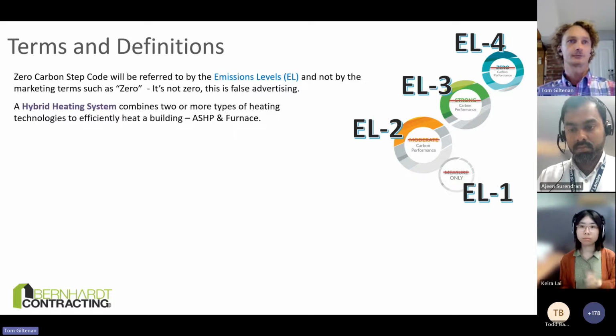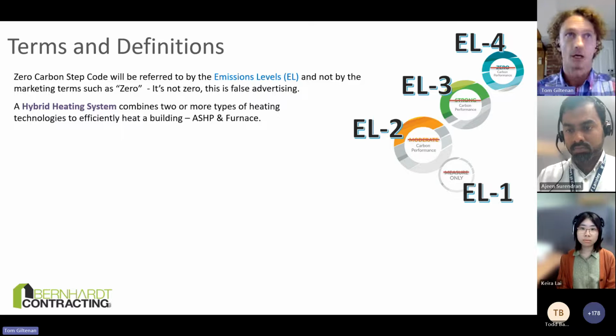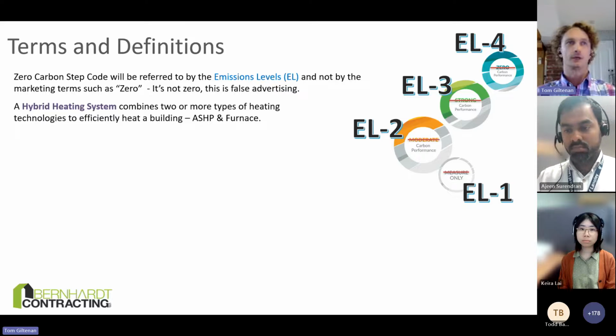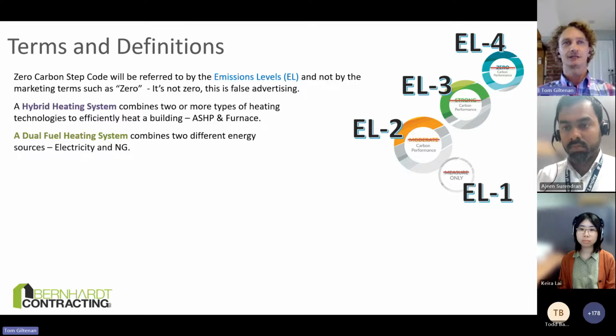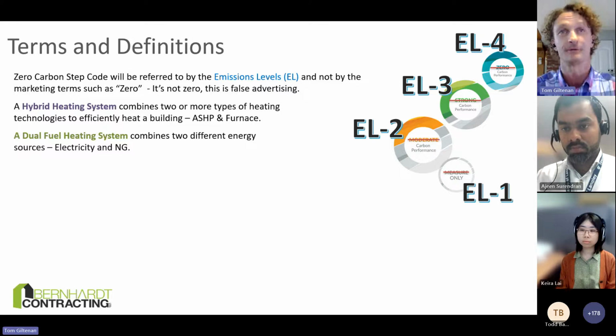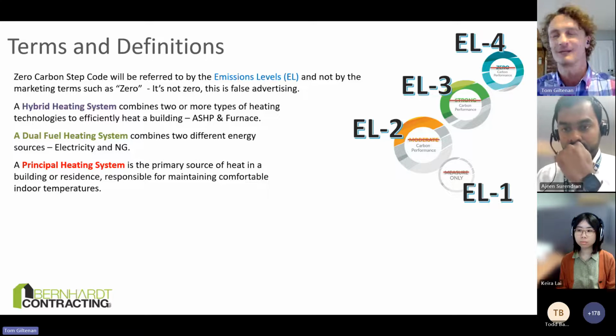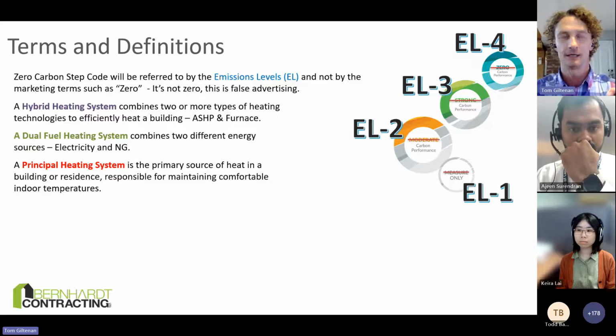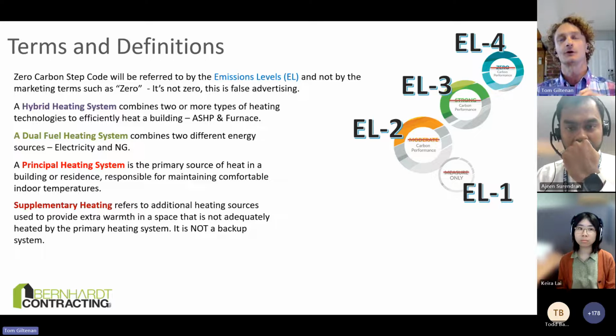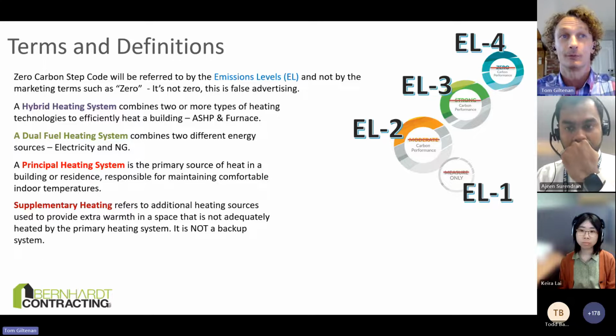A hybrid system combines 2 or more space heating technologies. So this could be like a heat pump with a furnace. A dual fuel heating system is different in that it is using 2 different fuels. So electricity, natural gas. A principal heating system is your main heating system that does the majority of your heating. A supplementary system will come on when the primary system is not meeting the full threshold. This is not a backup system.